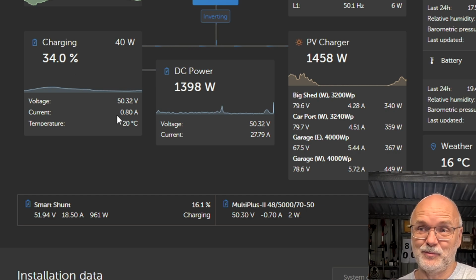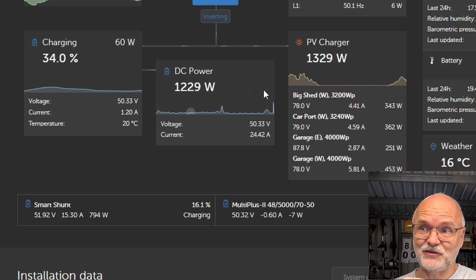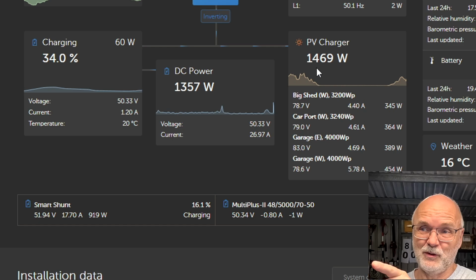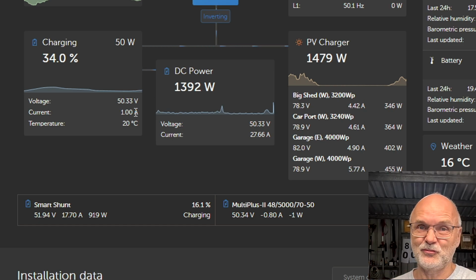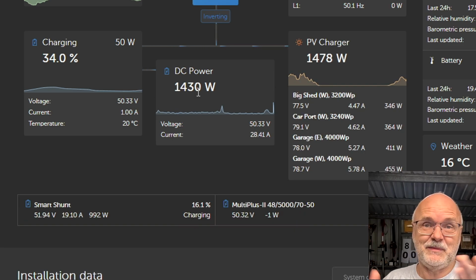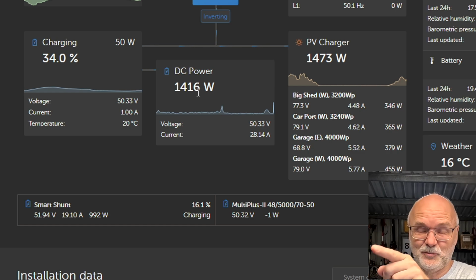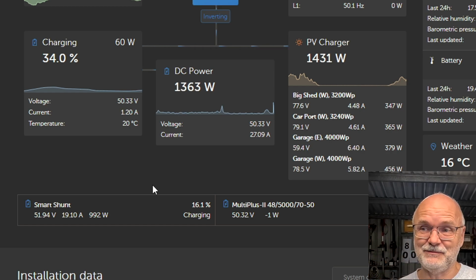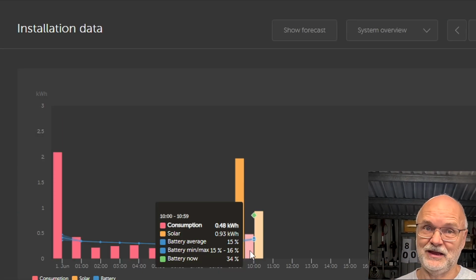Yep, it has now. So now we are showing the data of the JK BMS. We can see only the 0.8 amps coming in from the tilt system. And now the system assumes again we are charging from solar with 1.4 kilowatts, but we are only charging 1.2 in the battery. The rest must be DC power.